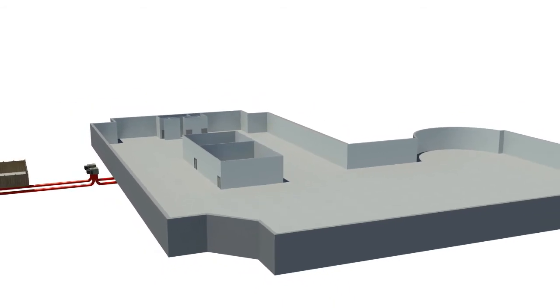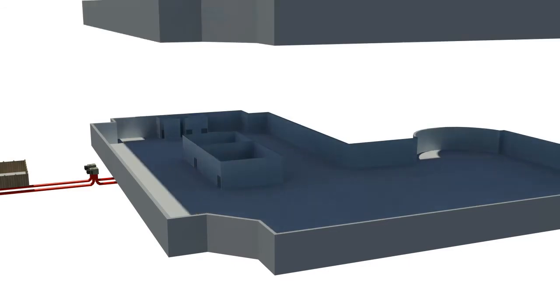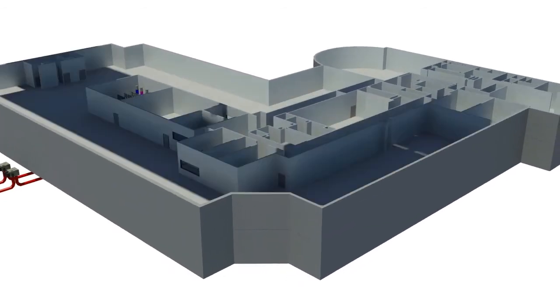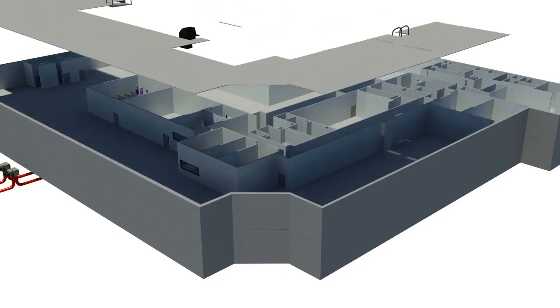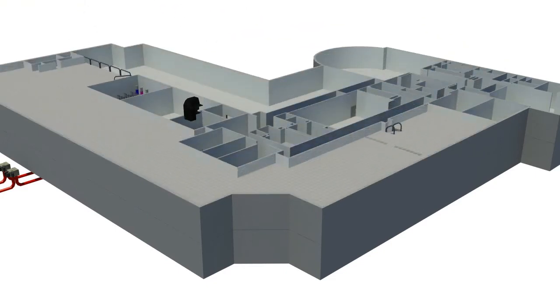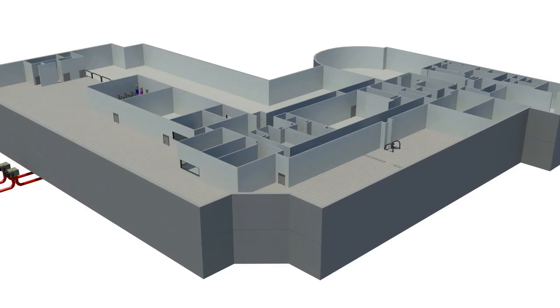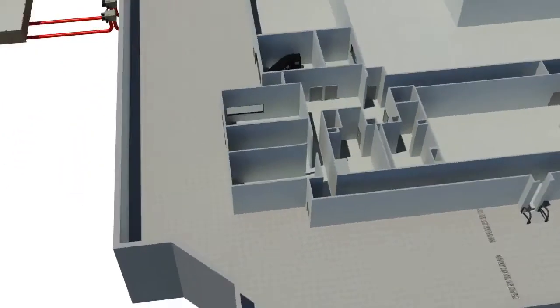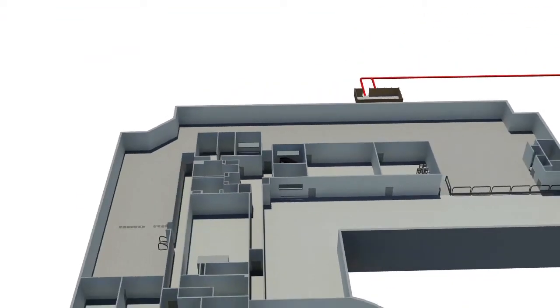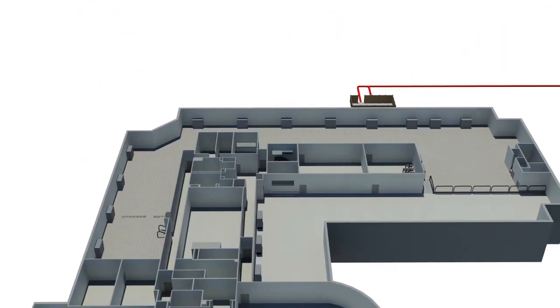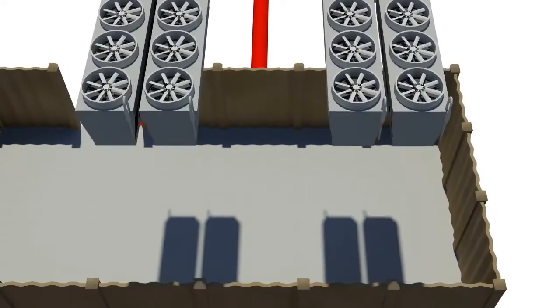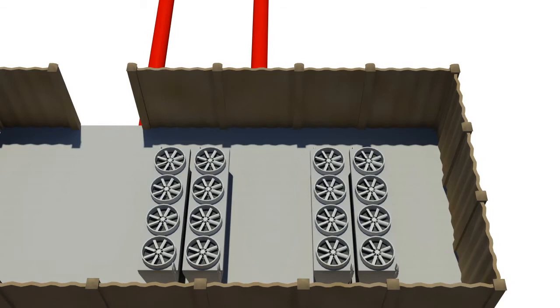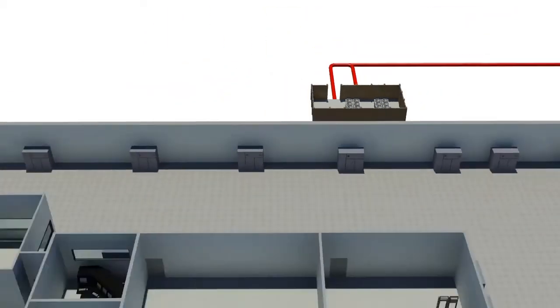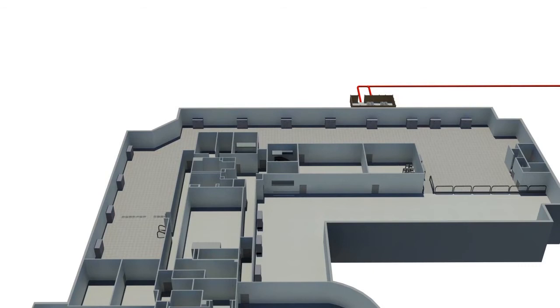The inside of the data center is intricately engineered to provide an optimal operating temperature at all times. 6,000 square feet of the total 38,000 square feet facility are engineered with 12-inch raised floors to circulate cool, temperature-controlled air into server rooms through floor-level ventilation systems. 28 airflow computer room air conditioning CRAC units with 450 tons of cooling are positioned throughout the facility in an N+1 configuration.